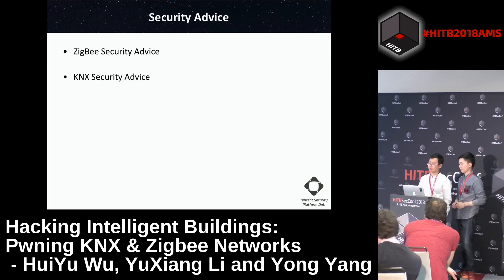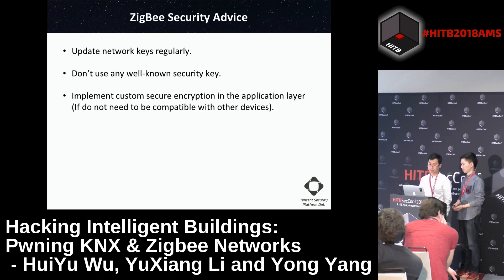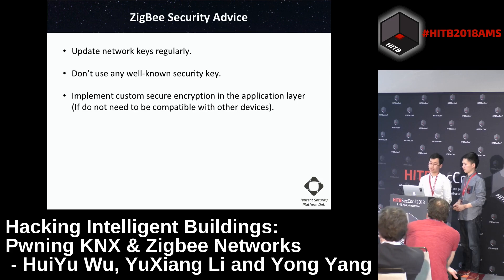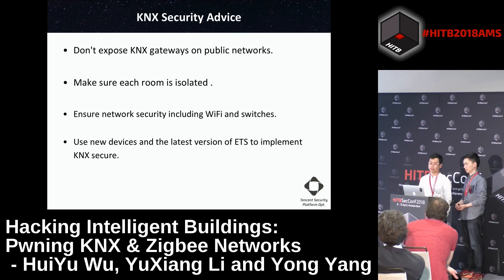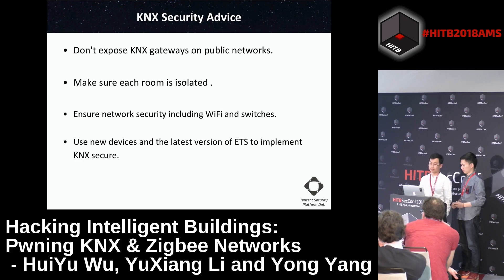In the final section, we provide some security advice on ZigBee and KNX networks. For ZigBee: update network keys regularly, don't use any well-known default key, and implement custom secure encryption in the application layer. For KNX: don't expose KNX gateways on public networks, make sure each room is isolated, ensure network security including Wi-Fi and switch security, use new devices and the latest version of ETS, and implement KNX Secure.